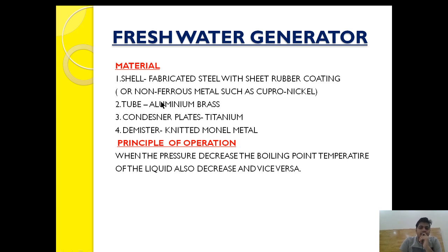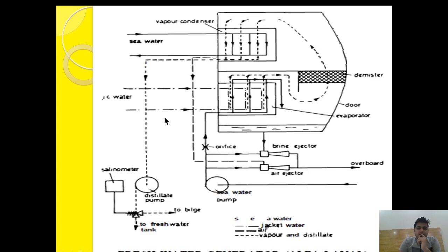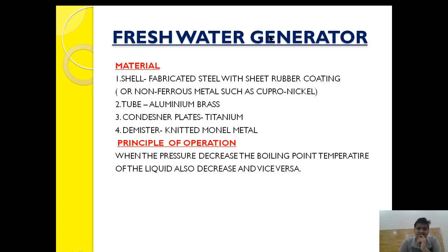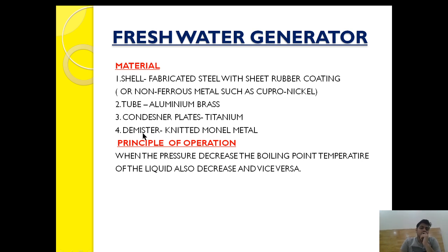The tubes used for heat exchange purpose are made up of admiralty brass. The condenser plate is made up of titanium — in some cases both the condenser plate tubes as well as the evaporator plate are made up of titanium. Demisters are made up of knitted Monel metal.